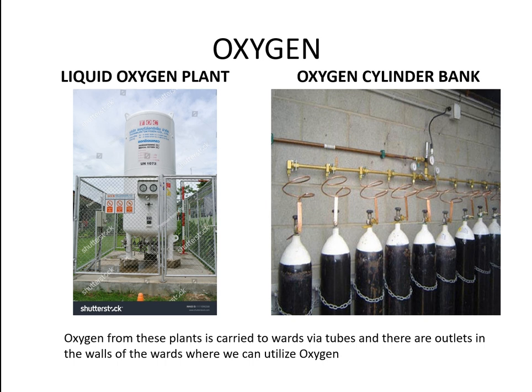A certain plant may contain liquid oxygen and another plant may contain an oxygen cylinder bank. In a liquid oxygen plant, the oxygen is stored as liquid oxygen and can be converted into gaseous oxygen. On the other hand, an oxygen cylinder bank is a particular place in a hospital where lots of oxygen cylinders are stored, and these cylinders can provide oxygen.